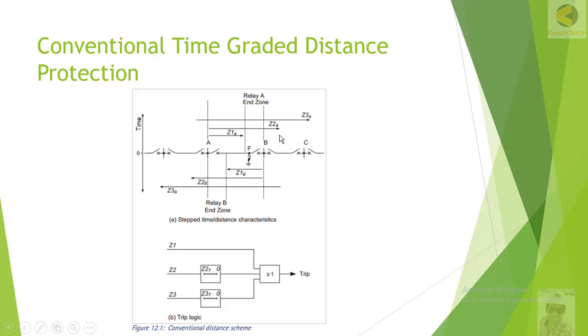If we set Zone 1 to 100% between A and B, and there is a fault near the breaker — within 5% of the line at the far end — the relay at Station A might overreach due to CT error, VT error, or variable arc resistance. It might trip in Zone 1 for a fault that is actually beyond the protected line, which is not required and will increase instability.